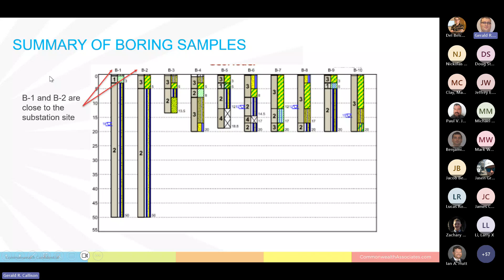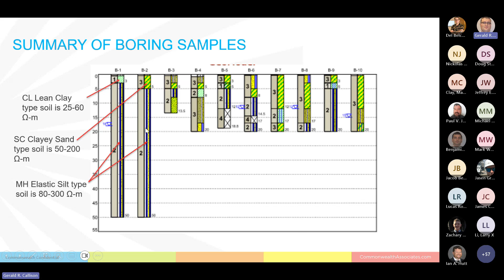Now the problem is, B1 and B2, we looked at them because they were close to the substation. We see a little difference up top, but similar stuff below, less variation below than up top. What we see is lean clay is about 25 to 60 ohm meters, sandy clay is 50 to 200 ohm meters, and this MH elastic silt is 80 to 300. So we want to be conservative, go a little on the upper end. Let's say a typical model we'd expect would be about 3 to 5 feet of maybe 100-200 ohm meters above, and above that 300 ohm meters.